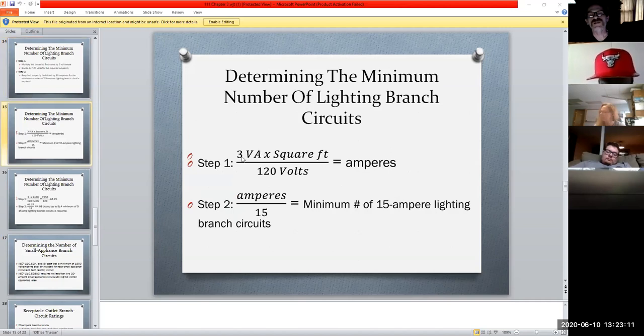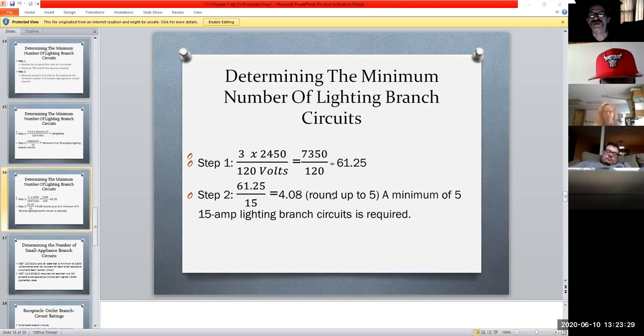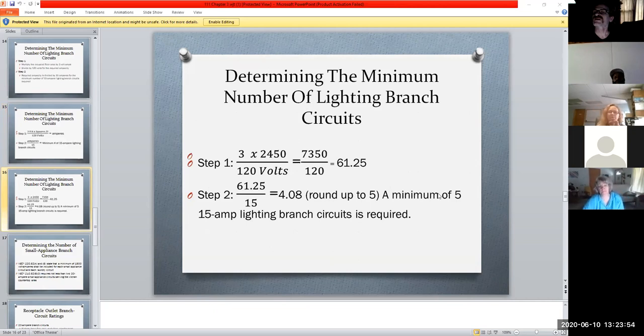Here's how the formula works. 3 VA times your square footage divided by 120 gives you the amperes delivered. Amperes delivered divided by 15 gives us the minimum number of lighting branch circuits we need in our house. When we get a result like this, we round up. Even though the number is small, like in this case 4.08, we still round up to 5. So for this house, we need 5 15 amp lighting branch circuits. Again, we're dealing with 2,450 square feet, which is a pretty good size. So we would have 5 different circuit breakers dedicated to lights, and there'll be feeders going out, depending on how we do the layouts. But that is what our number is going to be.